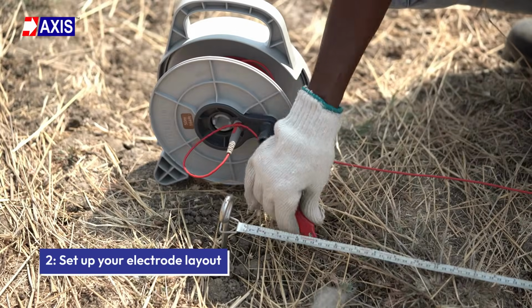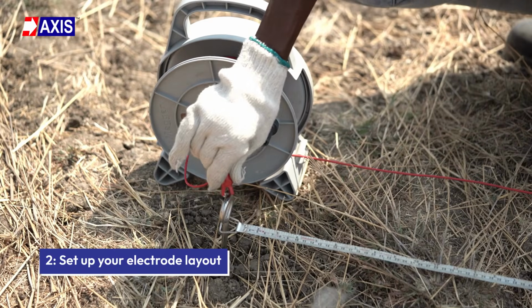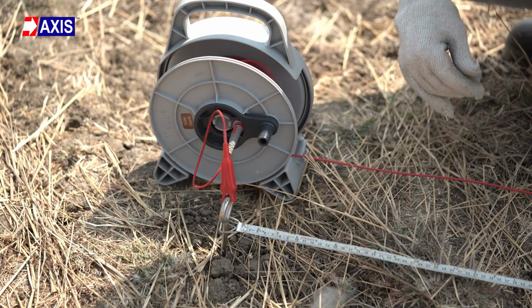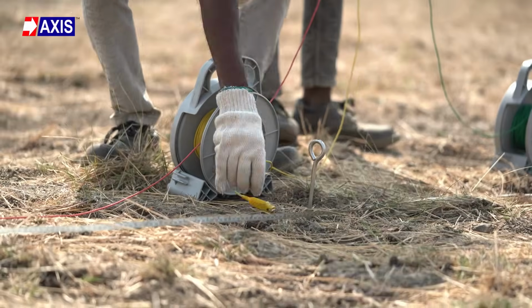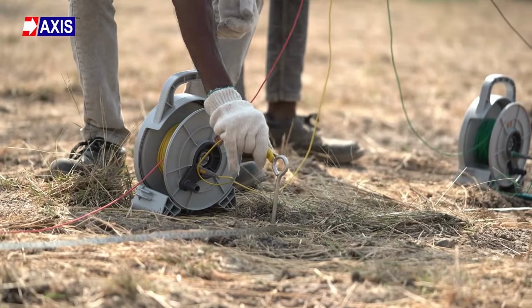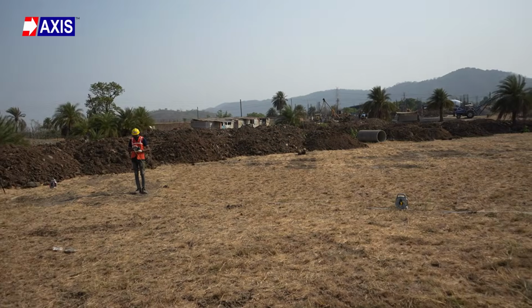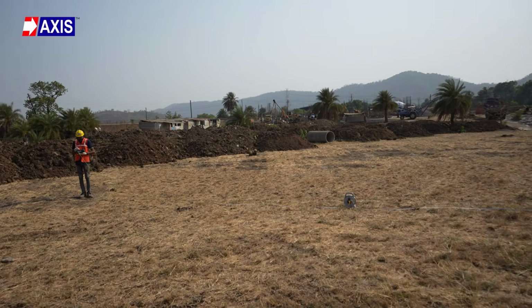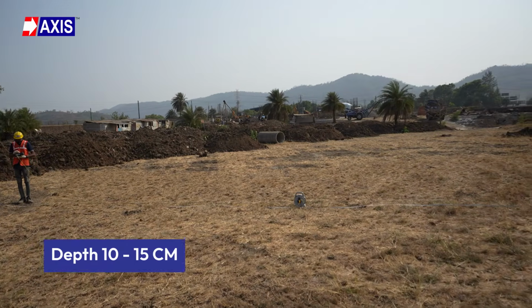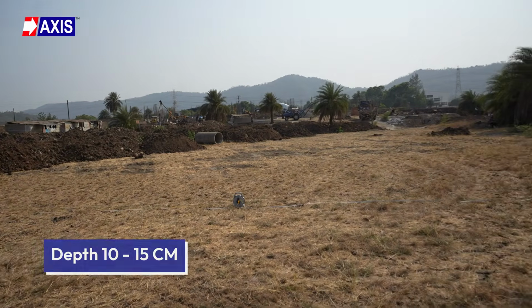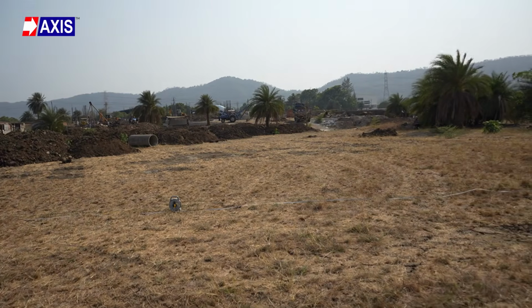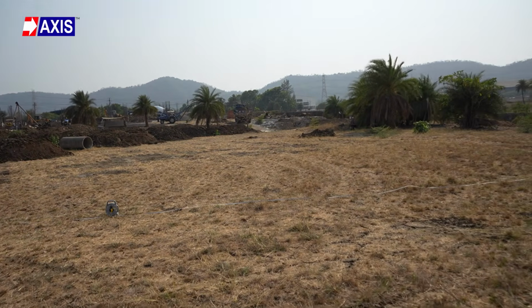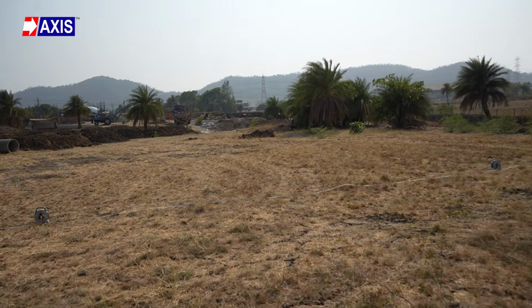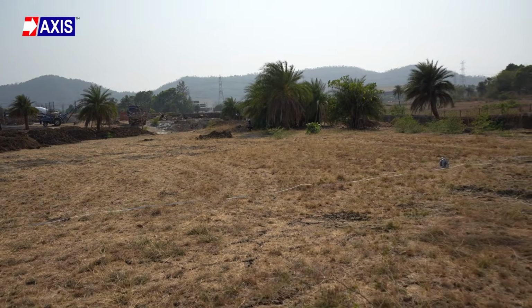Step 2. Set up your electrode layout. At the selected test site, drive all 4 electrodes into the ground in a straight line at equal intervals. The depth of each electrode in the ground should be between 10 and 15 centimeters. You choose the spacing between each electrode, and this spacing is what determines the depth of soil you are measuring.